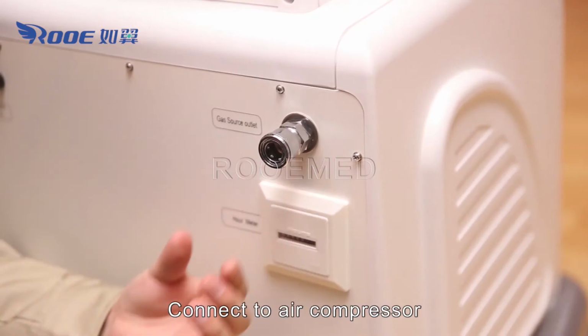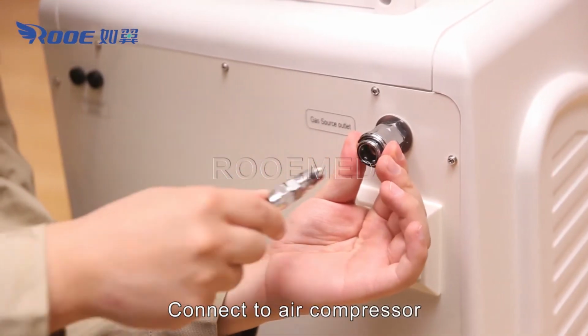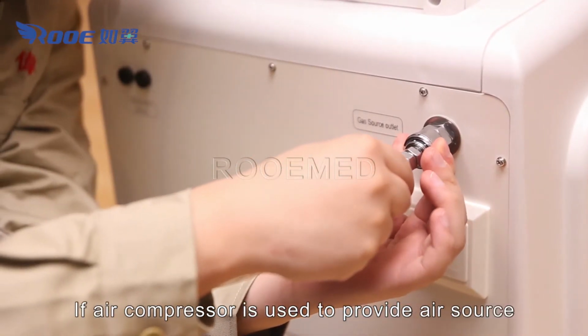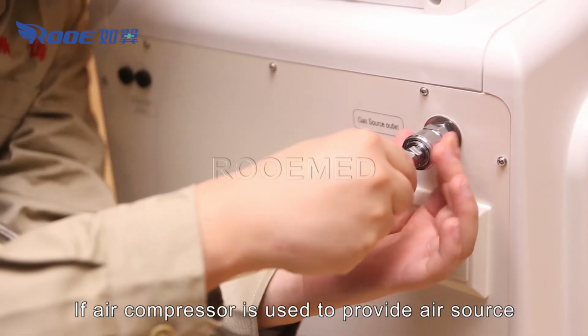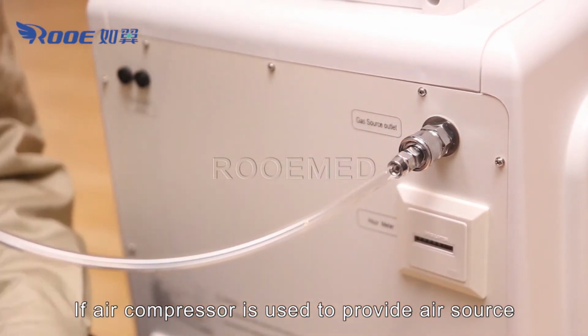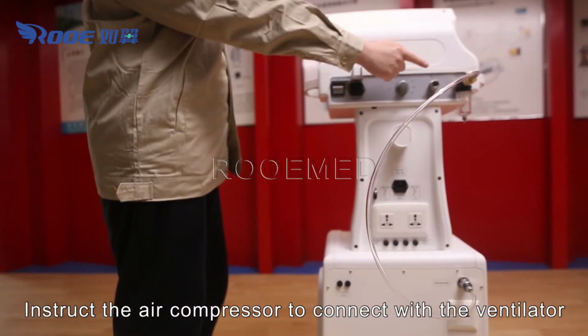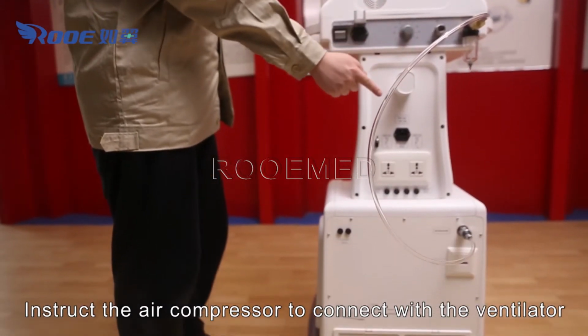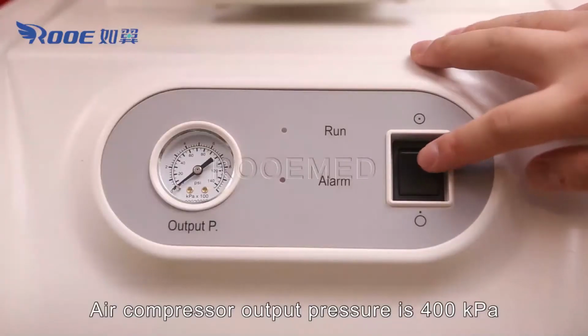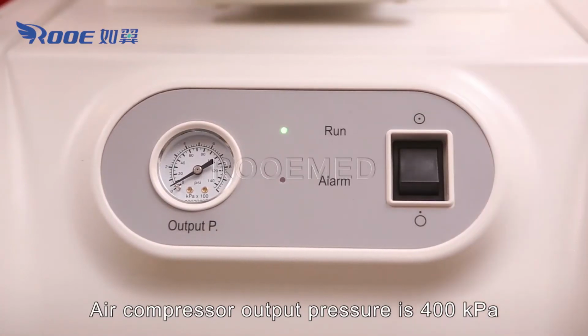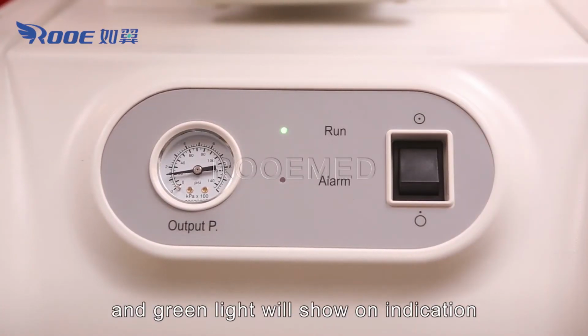Connect to air compressor. If an air compressor is used to provide the air source, connect the air compressor to the ventilator. The air compressor output pressure is 400 kPa, and a green light will show on the indicator.